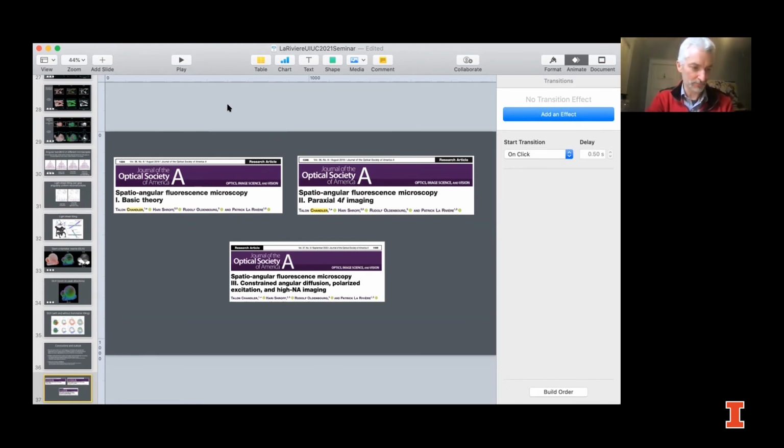I mean, there are some interesting problems where people use the dye's ability to rotate to report something about the viscosity of the environment that it's found in. And there are some classic bulk, non-imaging fluorescence anisotropy methods that rely on that. But we've mostly been thinking in terms of imaging oriented structures. So having these linkers be as rigid as possible is key, because if your dye is flopping around, that's a source of blur on your angular resolution.